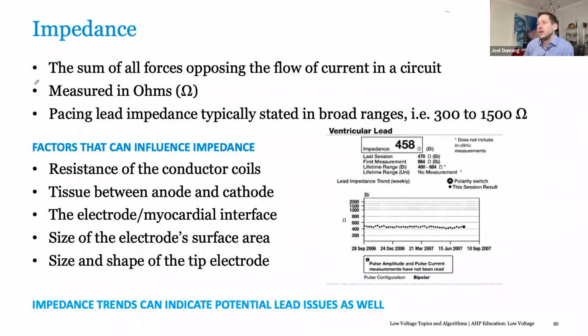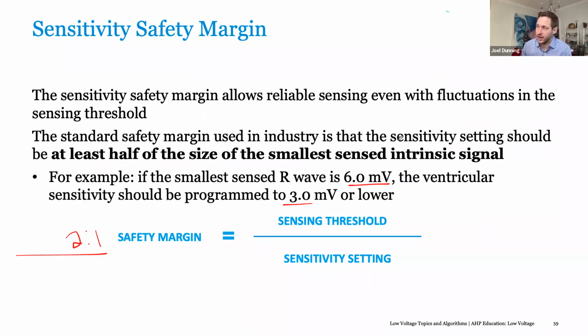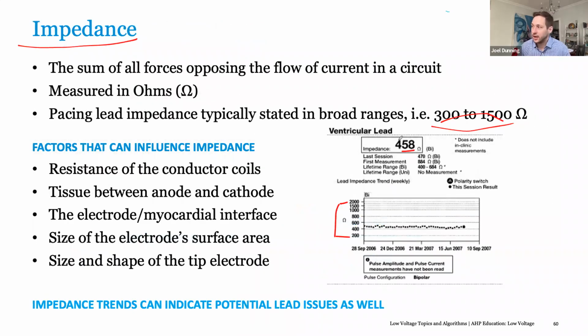So, all right. Now we talk about impedance. Impedance is one of the best ways to evaluate your lead integrity. Basically, impedance is the measure of resistance to the flow of electrons within the circuit, right? And what the value of the impedance is, as long as it's within reason, generally between, in this case it said 300 and 1500, but 200 and 2000 is also what you'll see. Generally, you'll see the impedance somewhere in this range. If it gets below, then we're in trouble. But the actual number itself matters less than the consistency of the impedance.